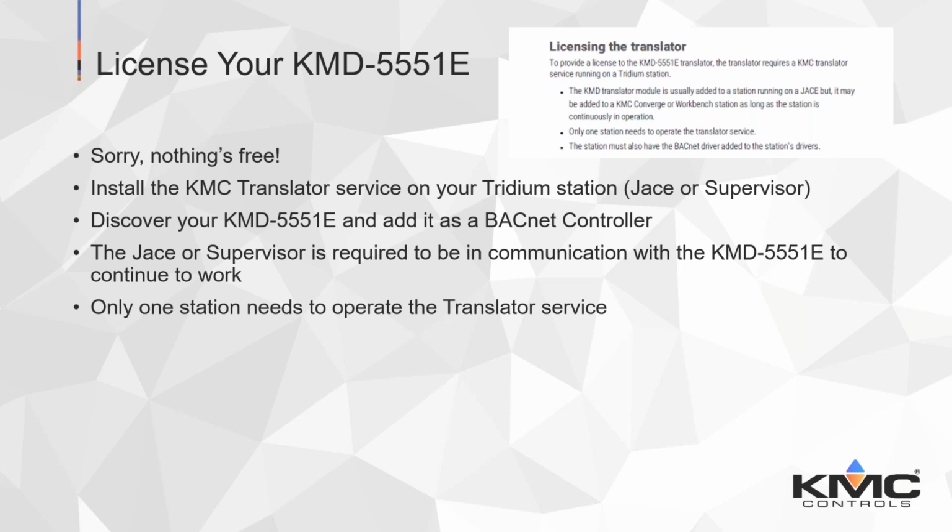Are there any other points in the translator that Niagara or Commander would be interested in, or are we just adding it as a device to keep the license alive? Just adding it as a device. There's nothing inside that you can pull out of the translator. So all of the virtual devices it's hosting are discovered separately as generic BACnet devices in Niagara.